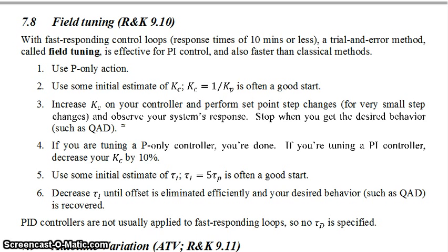Now if you're using a PI controller, what you'll want to do is tune your tau_I. So now you'll switch to proportional integral control. To do that, first you decrease your K_C by 10%. Then you use some initial estimate of tau_I. Tau_I equaling 5 times the process time constant is often a good start as your initial estimate.